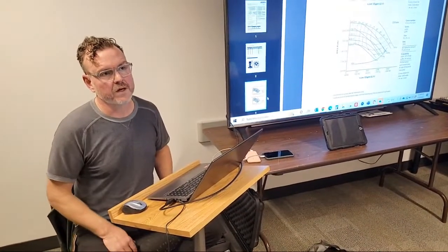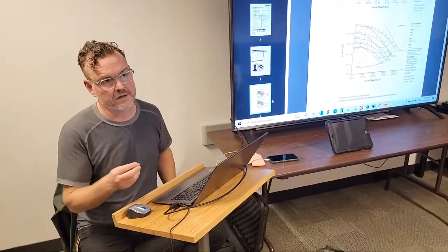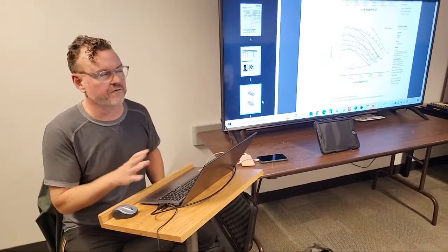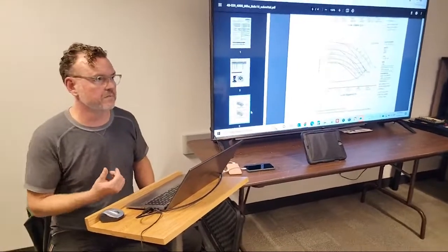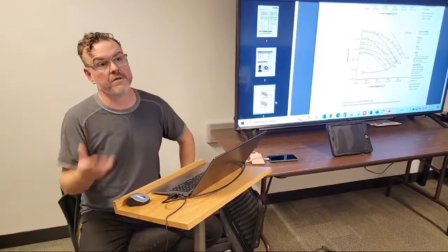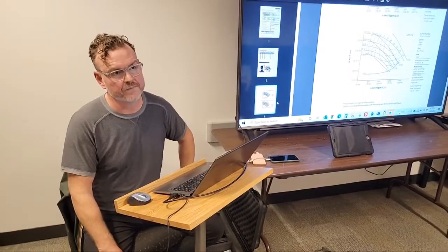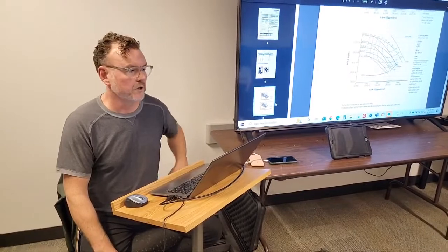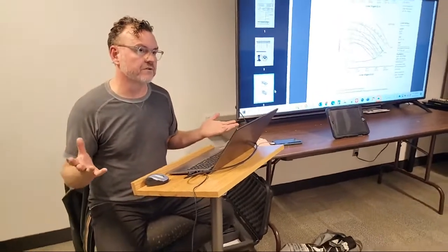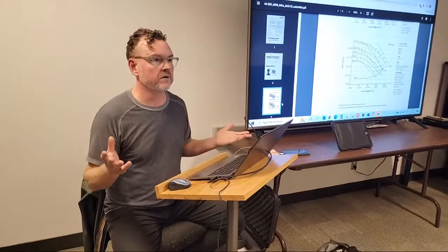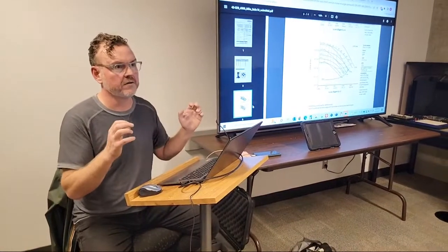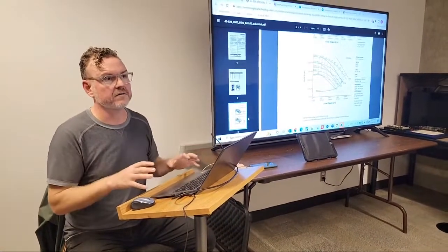So there are other objects, and then there are different controls, different control strategies. There's BACnet, Modbus, LonWorks, N2, but BACnet seems to be the one that's really taking off. Basically I can have five different manufacturers from anywhere in the world, put them in one mechanical room, and then we get the building automation and everybody's talking BACnet, right?